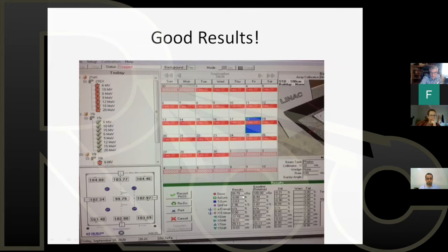Here's a good example here. Nothing is red. Everything has passed. Notice how it shows numbers at each detector, and you can see the effect of flatness here. So it's very close to 100 in the center, but look at this, 2.5%, almost 3%. So this is a measurement of beam flatness. And from diagonal to diagonal, look at the flatness. There's nothing wrong with that.